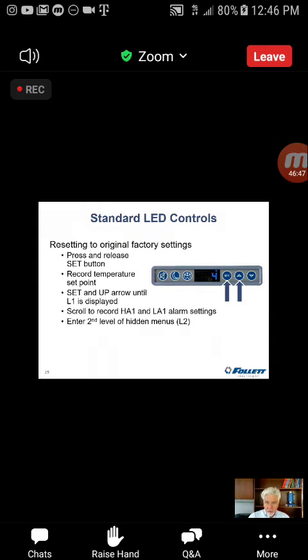And once we're in L2, we see L2 in the display, you're in level 2. We're going to scroll and we're going to go to the probe offset settings. This is how we calibrate the probe. The factory setting is 0 degrees. They are not offset at all. We'll be talking about probe validation in just a few minutes.